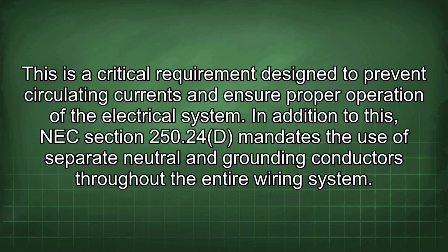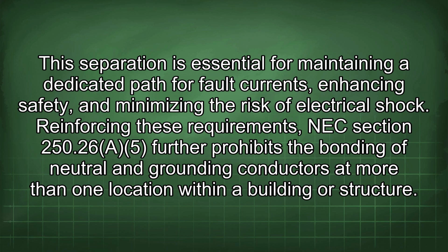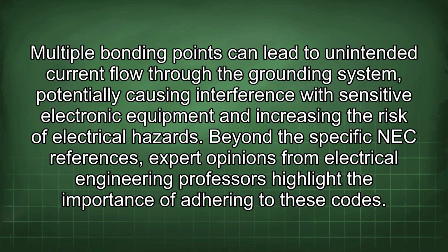In addition to this, NEC Section 250.24(D) mandates the use of separate neutral and grounding conductors throughout the entire wiring system. This separation is essential for maintaining a dedicated path for fault currents, enhancing safety, and minimizing the risk of electrical shock. Reinforcing these requirements, NEC Section 250.26 further prohibits the bonding of neutral and grounding conductors at more than one location within a building or structure. Multiple bonding points can lead to unintended current flow through the grounding system, potentially causing interference with sensitive electronic equipment and increasing the risk of electrical hazards.